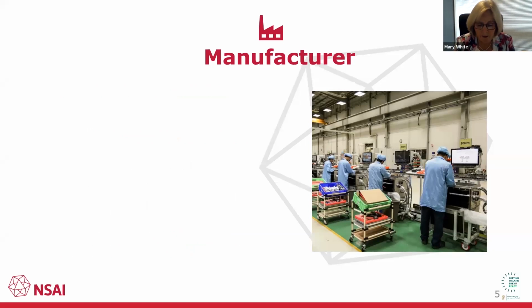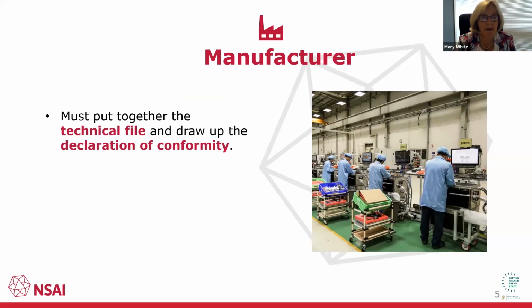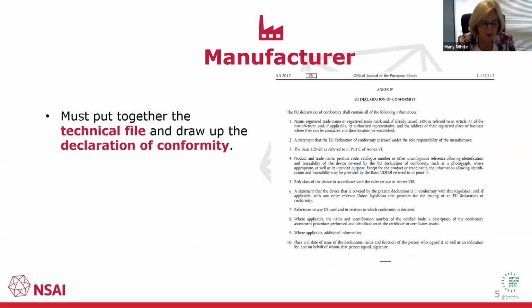The manufacturer must put together what's known as a technical file before he can draw up his declaration of conformity. This must include relevant design and manufacturing information, copies of all test results, the standards to which it is tested, and notified body certificates if required by EU law.